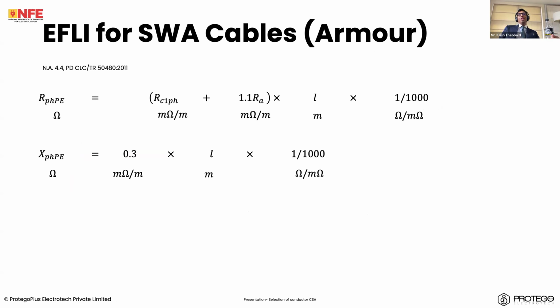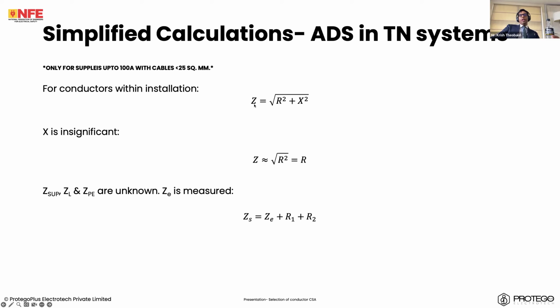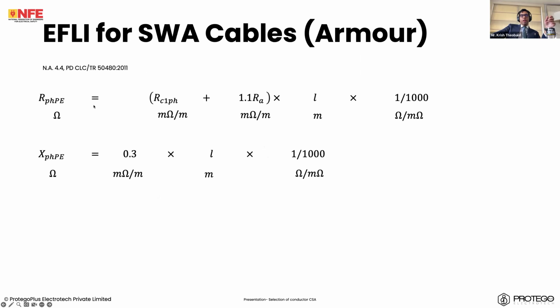So, how do we calculate the earth fault loop impedance? Now, we have to break up the reactive component and the resistive component, because we know that the impedance is equal to the square root of the resistance squared plus the reactance squared. In smaller cables, the resistance is the significant part, the reactance is almost nil. We can assume X is equal to zero and we just get Z is approximately R. But in larger cables, especially steel wire armored cables, this is a concern. So what do we do? Remember, break it down into the resistive component and the reactive component.